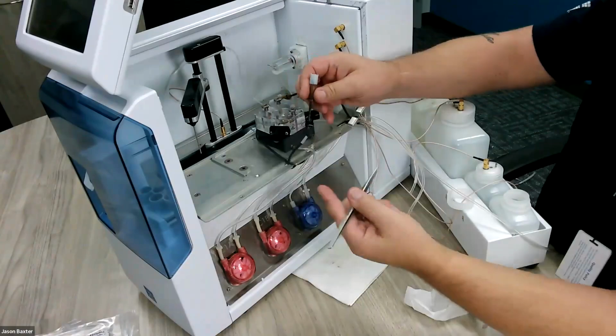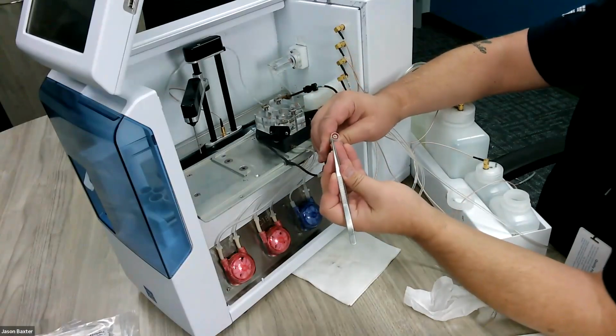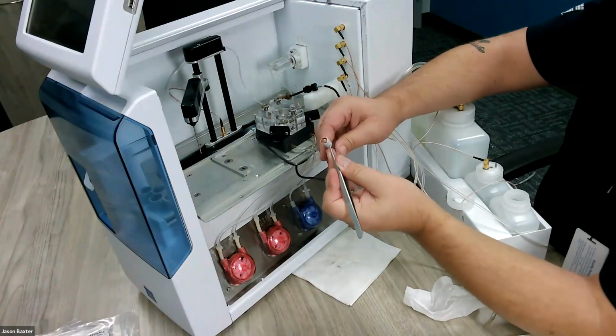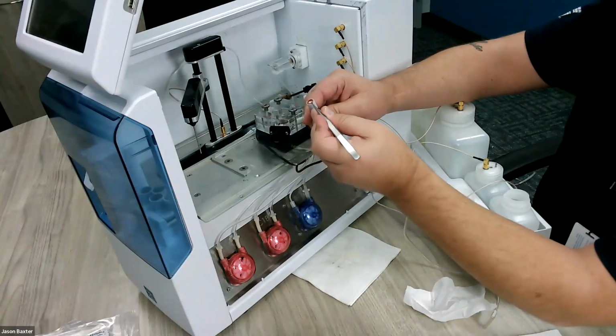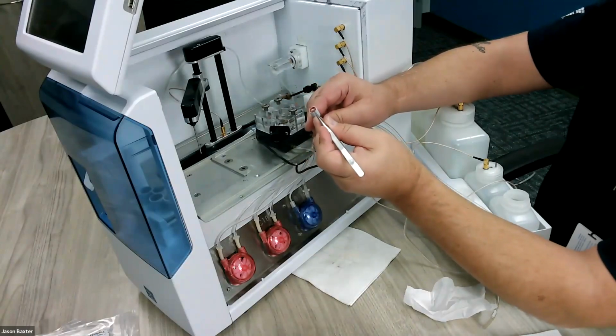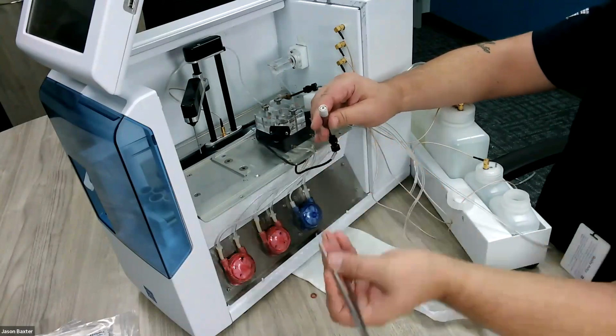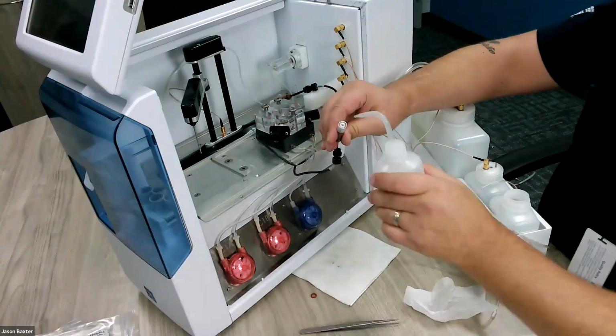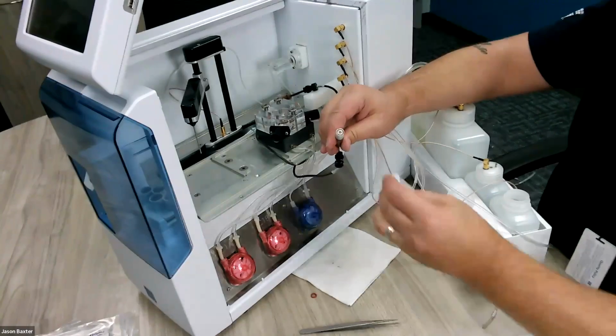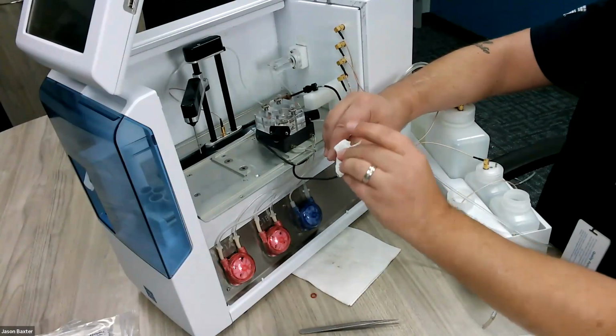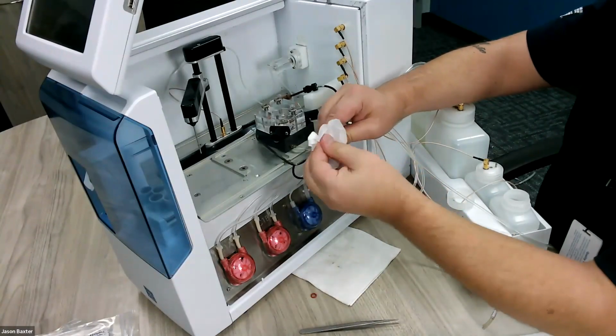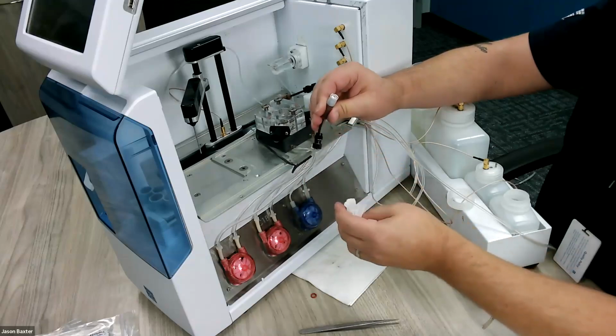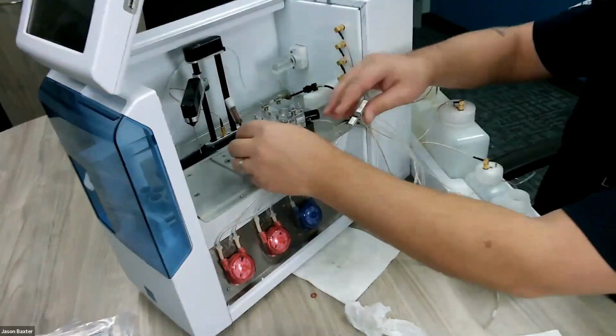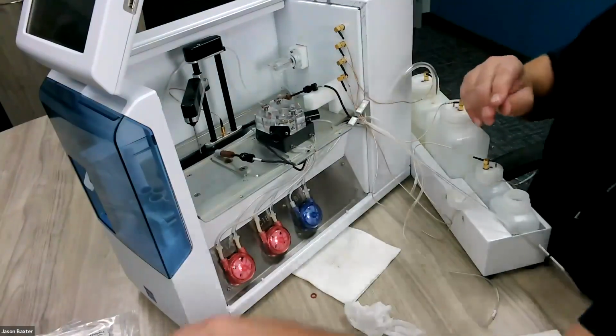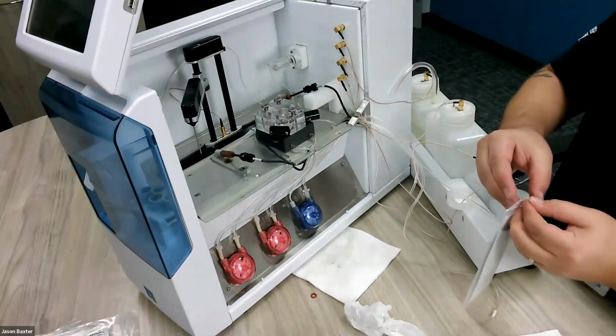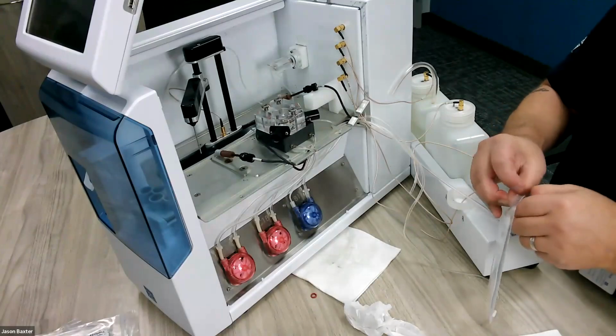Here's our A's on the left, so here's probe A. You'll notice that the probe housings have a small cutout, so you can get in here with a pair of tweezers or some other small object, maybe a paper clip, and you can just pop it out. Repeat as you did with the first probe. You want to make sure to get all of the IPA off of these electrode faces. The reason being is our membranes do not like IPA. The membranes will disintegrate almost instantly if they're exposed to IPA. And obviously, if you don't have a membrane, then the device is not going to work.